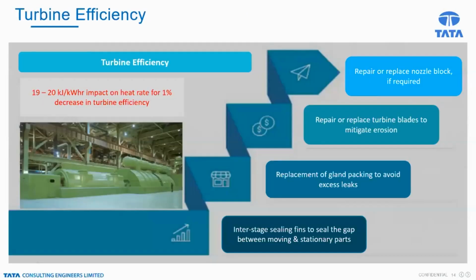The third one is the turbine efficiency. Of course, this is very important. Turbine cycle heat rate has a direct impact on the heat rate. For example, a 1% decrease in turbine efficiency at HP, IP and LP combined will have about 20 kilojoule per kilowatt hour impact. So this is also a huge value, and we have to see how we can minimize the losses.